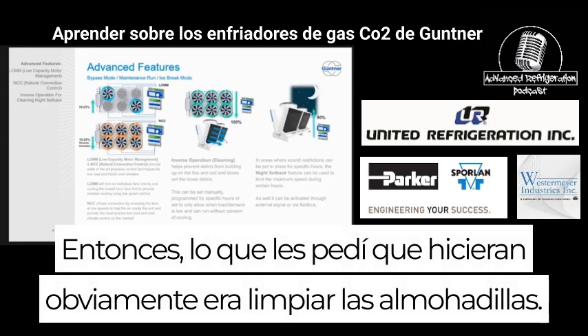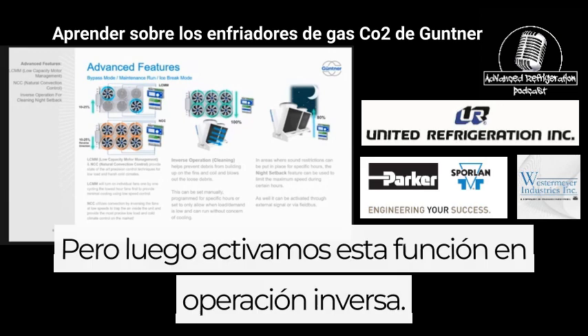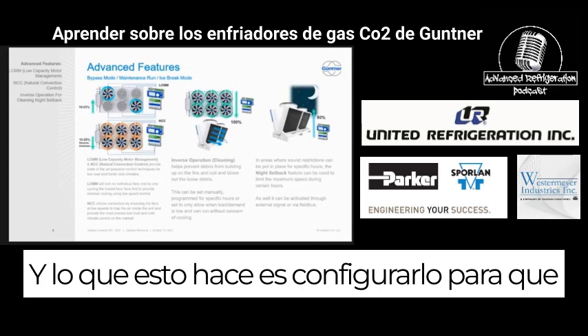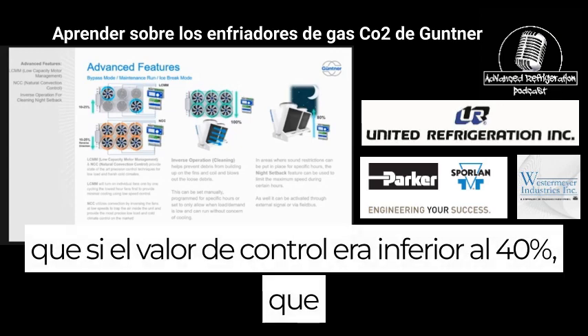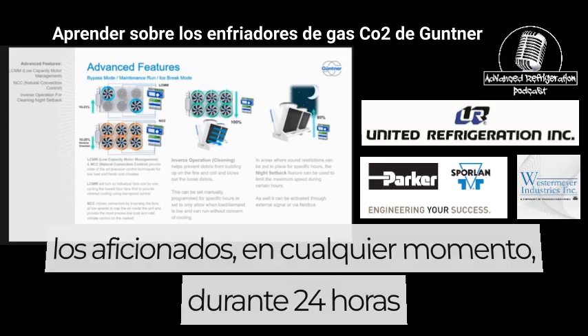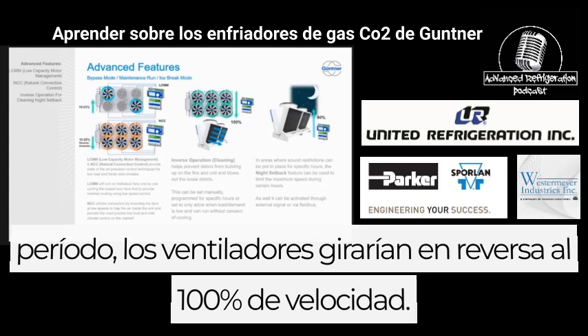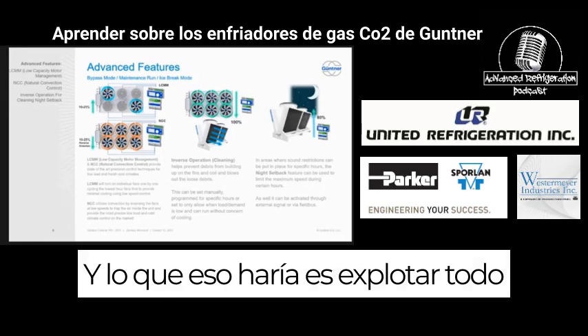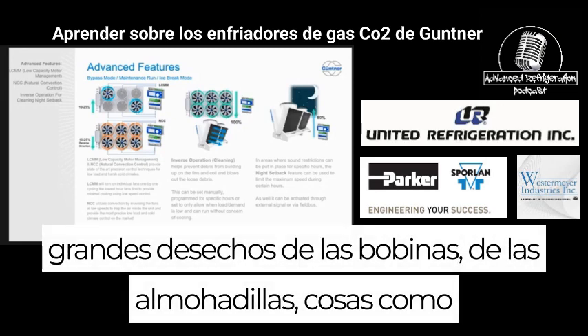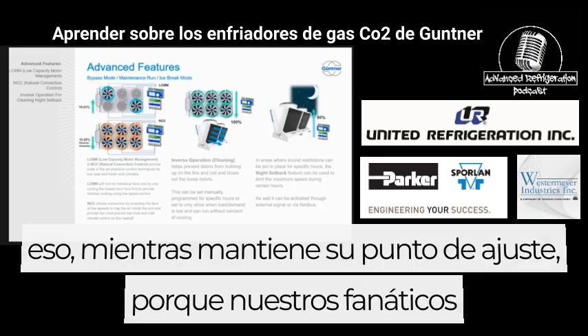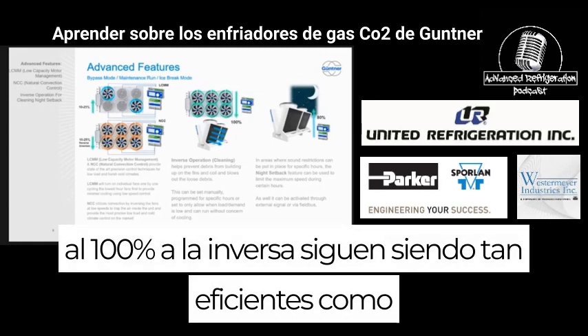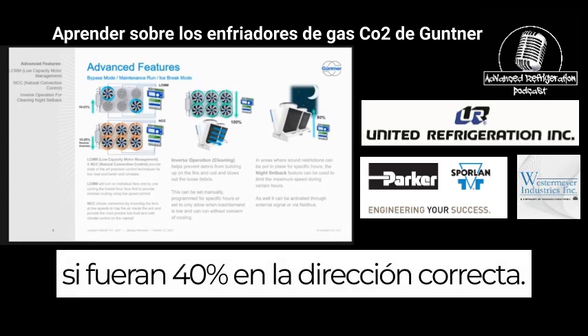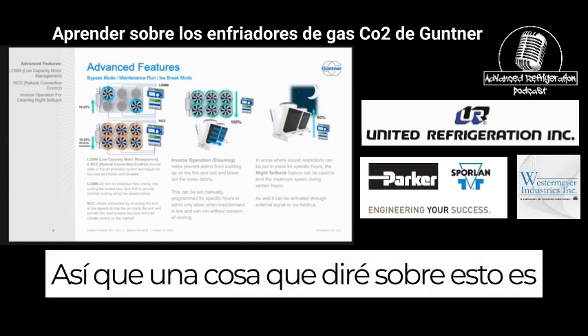So what I had them do is obviously clean the pads off, but then we turn this feature on, inverse operation. And what this does is we set it up so that if the control value was less than 40%, at any given period during a 24-hour period, the fan would spin in reverse at 100% speed. And what that would do is it blows out all large debris from the coils, from the pads, things like that, while still maintaining your set point. Because our fans at 100% in reverse are still just as efficient as if they were 40% in the right direction.